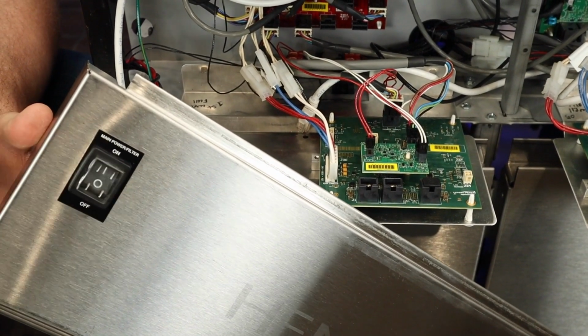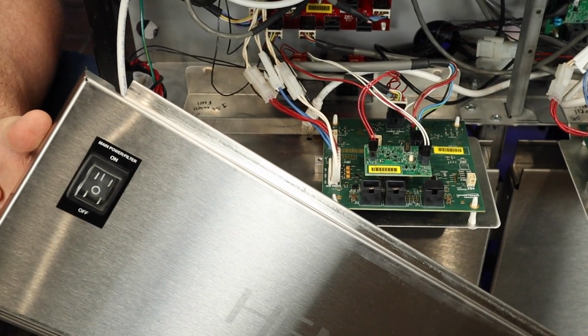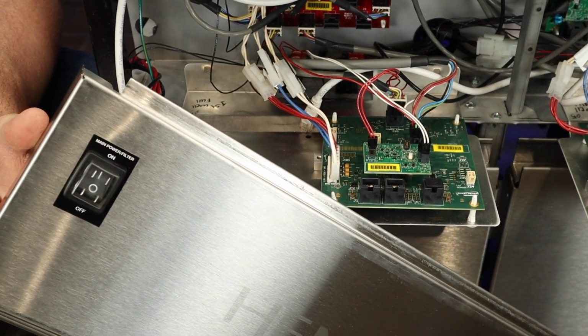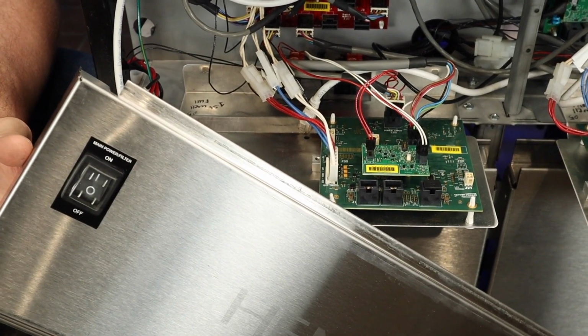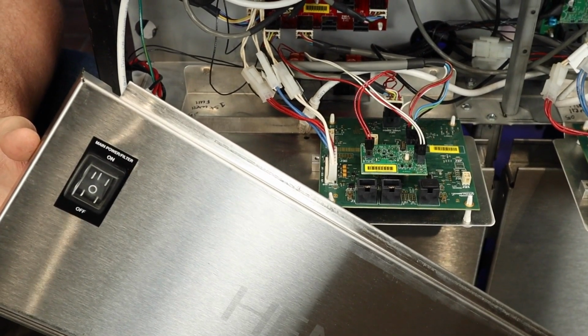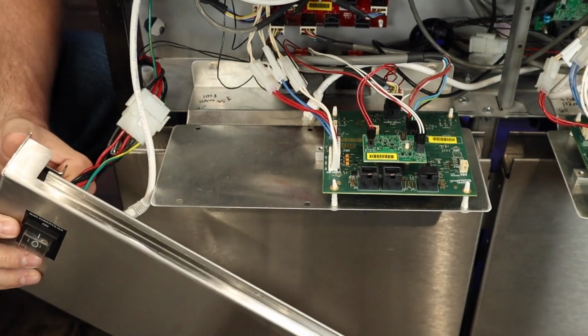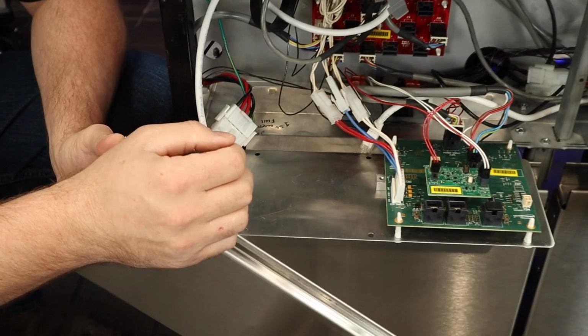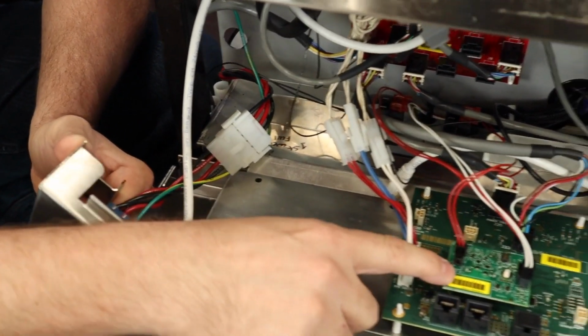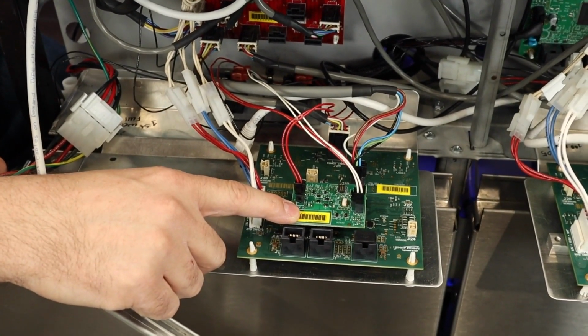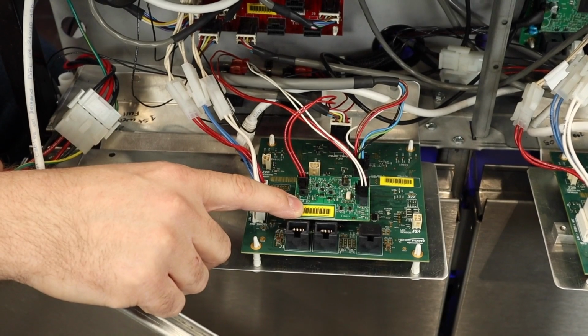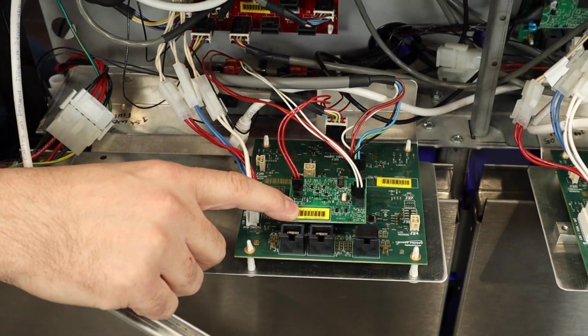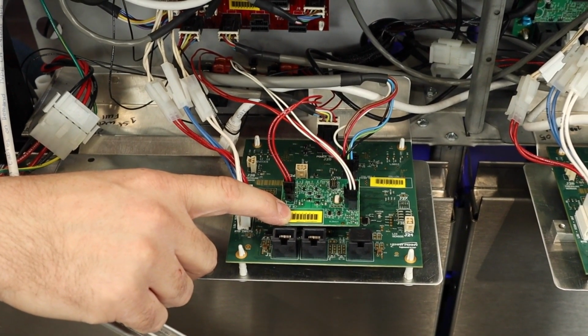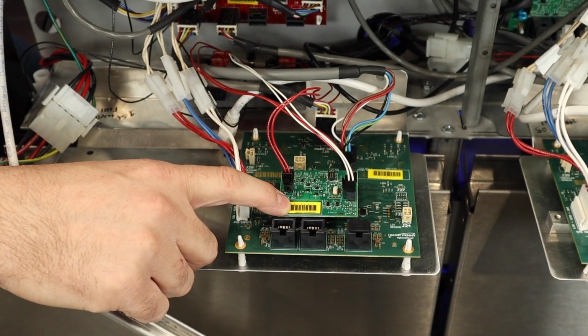So then we would go ahead and power it back on, and if that resets it, then we know the momentary reset switch is faulty. If that is not the problem, then we are left with two components, that being the high limit probe and then the high limit PCB. We first need to make sure that the probe is mounted securely and not all carboned up, as this will lead to future ongoing issues.